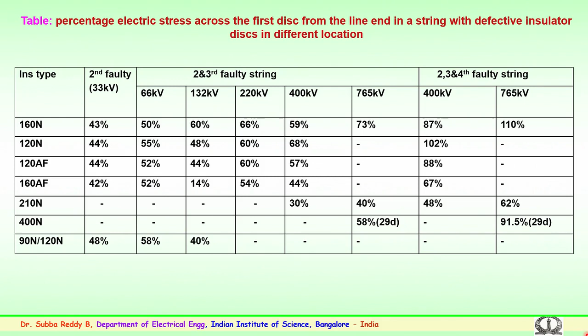So, here we have completed the ceramic disc insulators, the pollution phenomena, the methods employed for laboratory conditions, the cleaning of the insulator in the pre-monsoon and preventive maintenance, then the insulator discs which are faulty in the system, whether glass or porcelain, how proper care has to be taken by the utilities, and how serious the issue is in case the faulty discs are located at second, third or fourth, or in the middle or at the end of the insulator string.